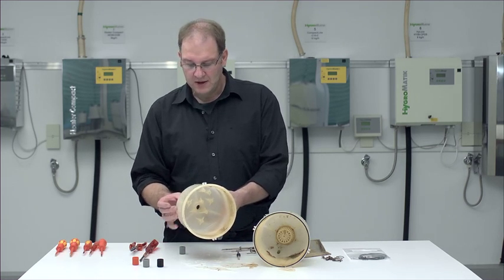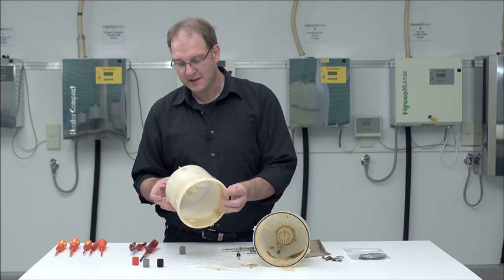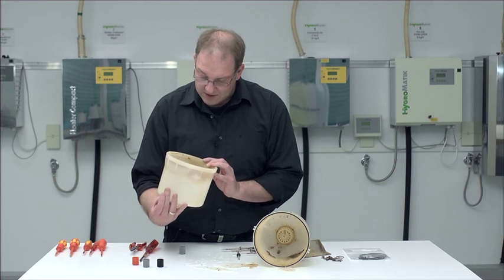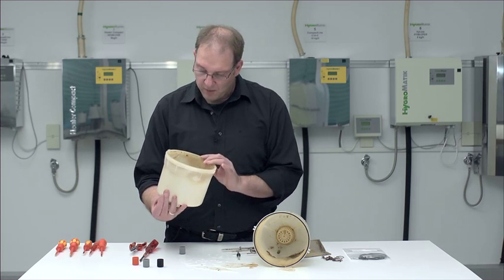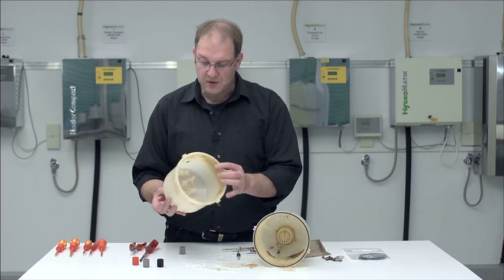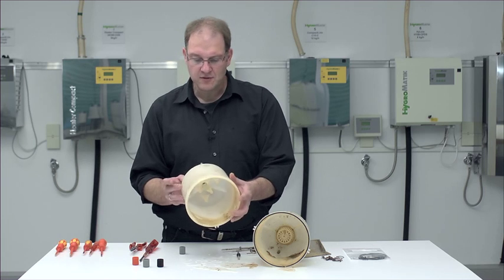I would really like to mention a certain point and that is to please also perform the cleaning at the top of and inside the cylinder because there too, minerals as well as salts can deposit and then sometimes connections with the sensor electrode could be generated which could possibly produce interfering signals.